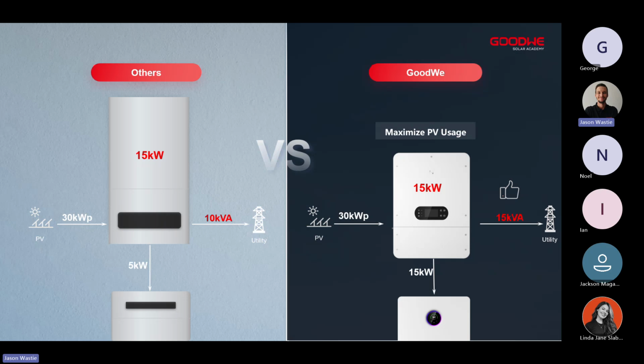Generally, when we look at a system, we have to take into consideration loss of efficiency, degradation over time of the panels, bad weather conditions, and that kind of thing. So we overpanel or we increase our DC capacity on the system. By doing that, there are limitations to some inverters, and those limitations don't allow you to get your full production out of the entire PV allocation that you've put on the system. With our inverter, we can use everything that we get. The batteries need to be charged and the loads are very high. We can do both at the same time and actually utilize our entire system.